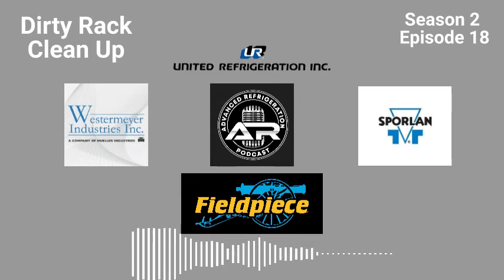Yeah, everything to do with how clean the system is, burnouts, just general cleanness. I've seen oil turn yellow just from the way the system is. Just because it's CO2 doesn't mean anything. It turns dark, it turns colors. We have 404 racks that are clear, and newer refrigerant racks that are clear. Usually when I see yellow oil, it's either dyed or it's had a bunch of burnouts in it.